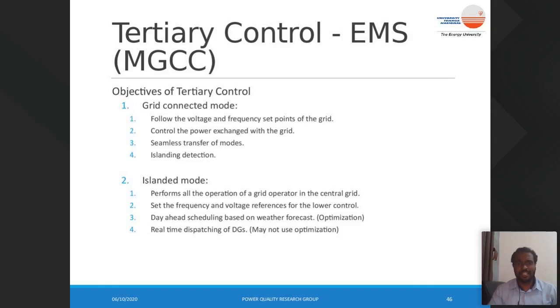The objectives of the tertiary controller vary based on the configuration or interconnection of the microgrid with the grid. For grid connected mode, the control is simple. It only controls the power exchange with the grid, when to exchange the power with the grid, and detects a problem with the upstream network and isolates the microgrid itself. And it just has to follow the voltage and frequency set points set by the grid operator. So it doesn't have any headache setting voltage and frequencies.